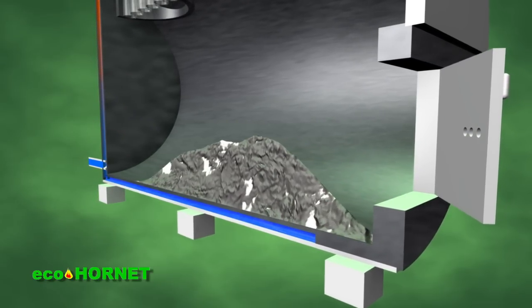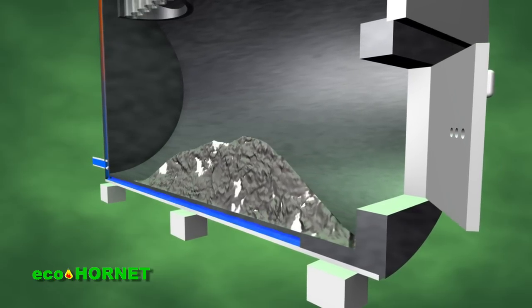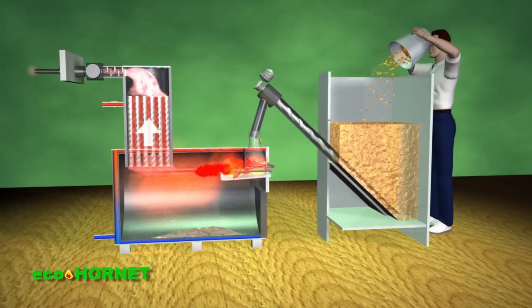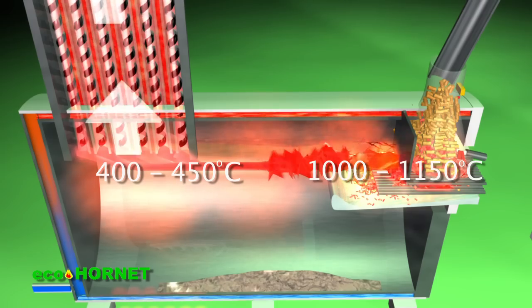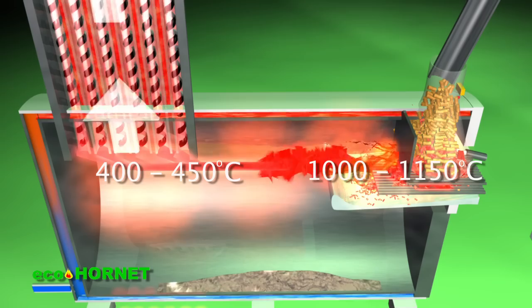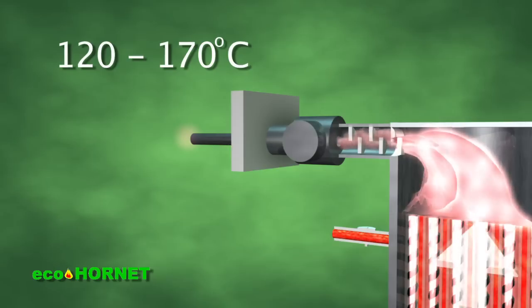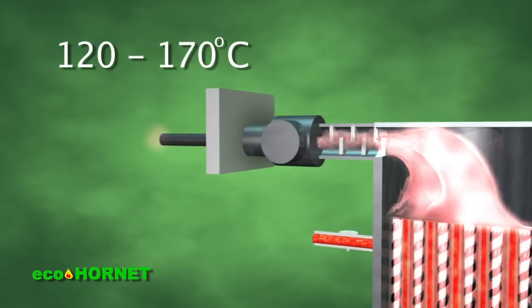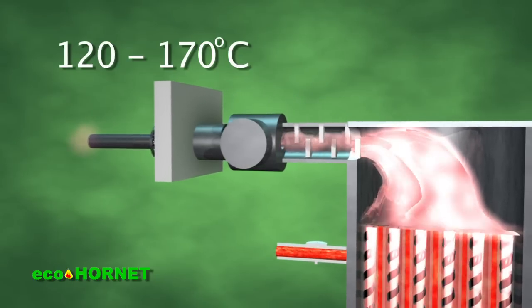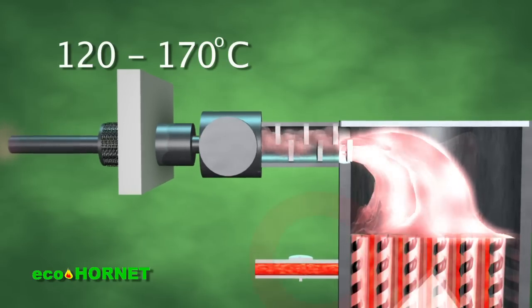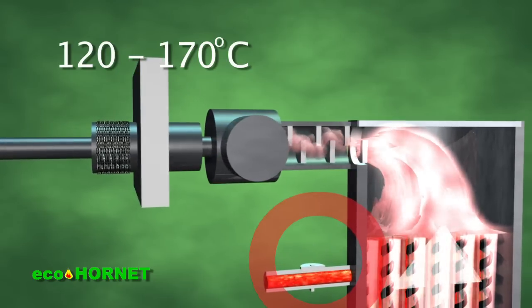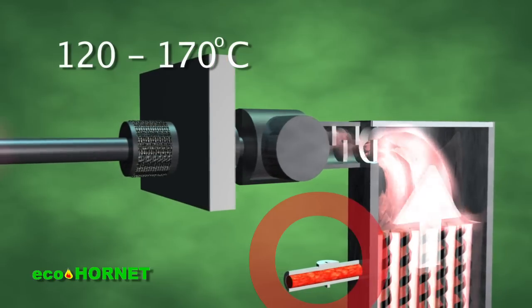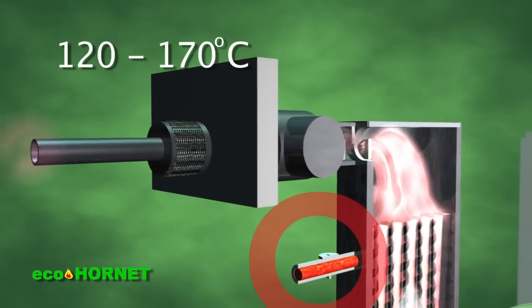The ash is disposed of every 30 days of operation. The burnt gas temperature varies: it reaches 1000 to 1150 degrees Celsius at its exit from the burner, 400 to 450 degrees Celsius upon entry in the convection area, and 120 to 170 degrees Celsius upon release into the atmosphere. The surface of the outgoing pipe for the heating agent is provided with a temperature thermocouple, providing information which is retrieved and processed by the automation system.